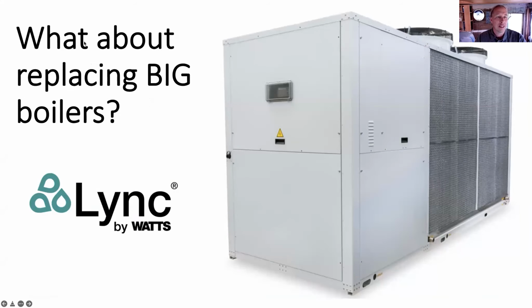Now, what about replacing big boilers that are doing 180 degree Fahrenheit hot water? A very common strategy in buildings in New York City, where they've got radiators everywhere. This produces 185 degree Fahrenheit water straight off the bat. It's a carbon dioxide heat pump that works down to -30, so you can have a polar vortex in New York City or wherever you're doing your architecture work. This is a cold climate solution, and really any climate solution. It's doing terrific work, and it's very resilient. You don't need to worry as much when you have one of these.